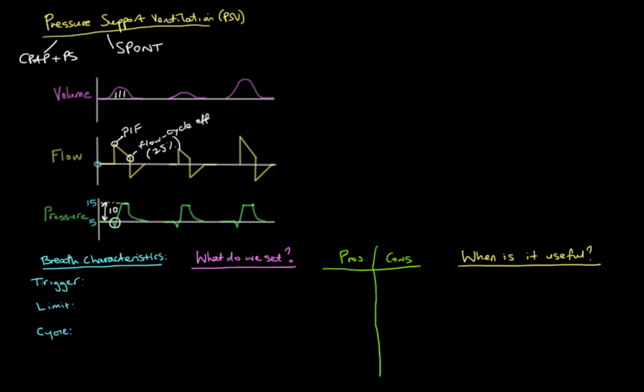Let's talk about the breath characteristics. The trigger variable — what causes the breath to begin — is patient effort. Specifically, it's due to a drop in the circuit pressure, so the variable is pressure. On some ventilators, you can also trigger using flow: if the patient generates enough of a change in flow in the circuit, it can trigger the breath. But it's going to be pressure or flow — usually pressure.